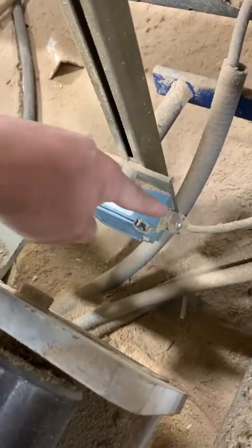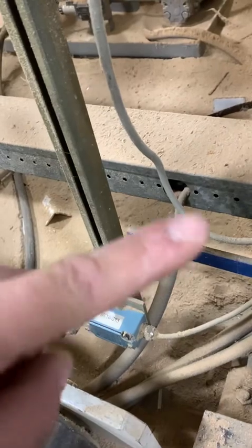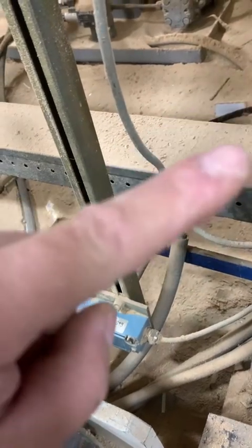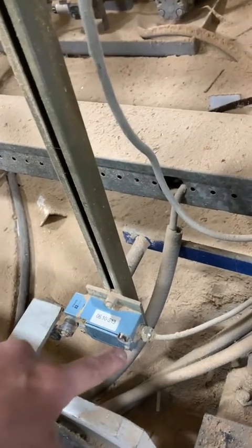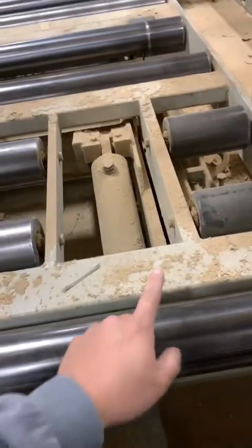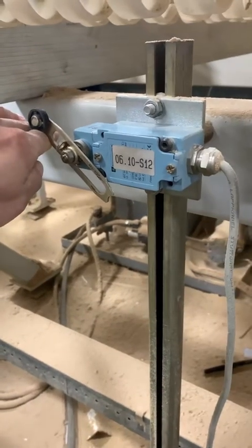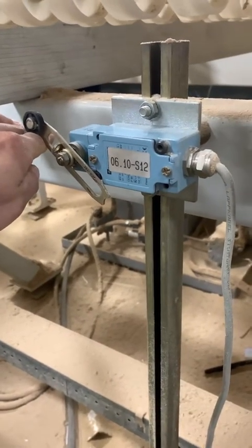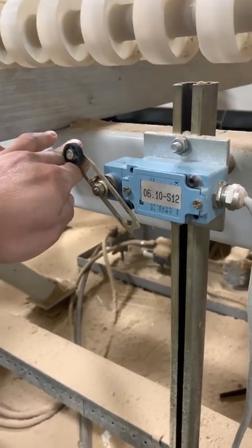So 24 volts comes into the normally open set of contacts in this limit switch, and then it goes back out to the PLC. It sends that 24 volts back to the PLC, letting the PLC know that it's all the way down. It's using that 24 volts back to the PLC as an input signal to the PLC. And if it would raise all the way up, it would then trigger and actuate the arm of this limit switch. And now it's going to send this 24 volts back to the PLC to let the PLC know that it is all the way up. You can continue with the sequence.